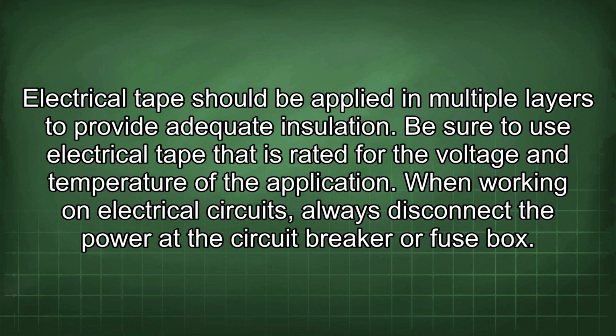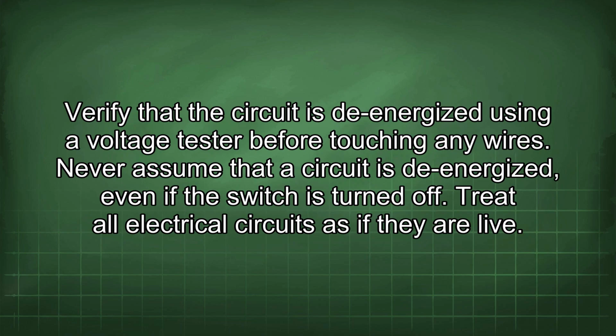When working on electrical circuits, always disconnect the power at the circuit breaker or fuse box. Verify that the circuit is de-energized using a voltage tester before touching any wires. Never assume that a circuit is de-energized even if the switch is turned off. Treat all electrical circuits as if they are live.